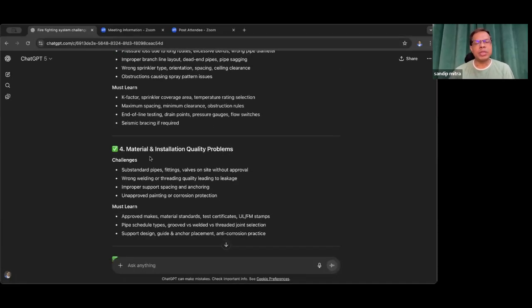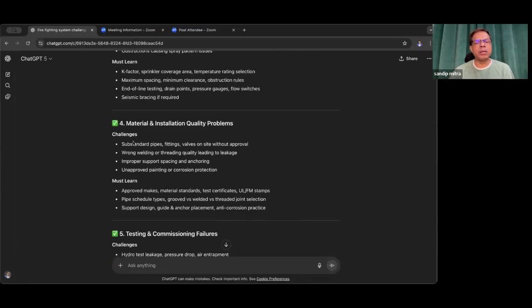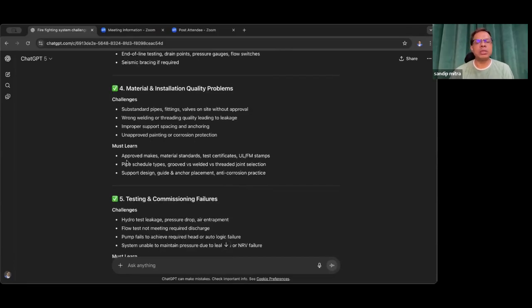And number 4, material and installation quality problems. Challenges: substandard pipes, fittings, valves on site without approval, maybe wrong welding or threading quality leading to leakage, improper support spacing and anchoring, unapproved painting or corrosion protection. Now what you need to learn? You will follow the approved make, material standards, test certificates, UL or FM stamps, pipe schedule types, grooved versus welded versus threaded joint selection, support design, guide and anchor placement, anti-corrosion practice.